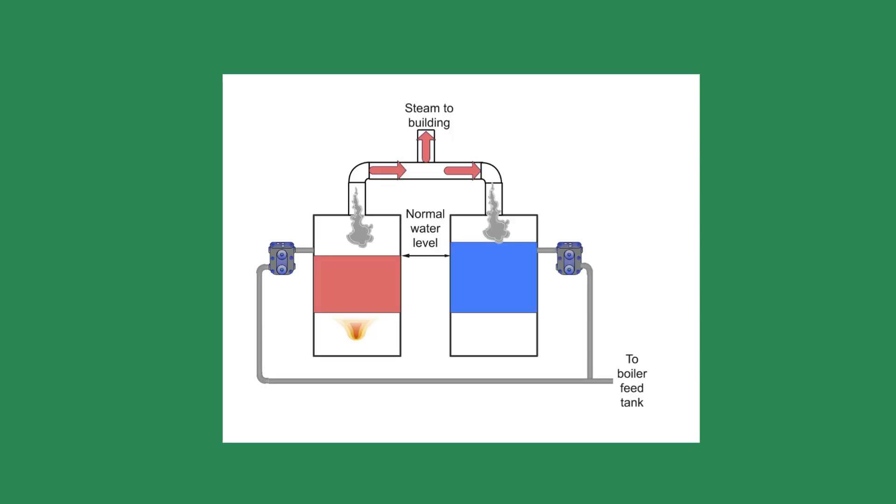As I looked at the steam system, I saw the reason. The boilers did not have high-level spill traps. The high-level spill trap is used to keep the lag boiler from flooding.